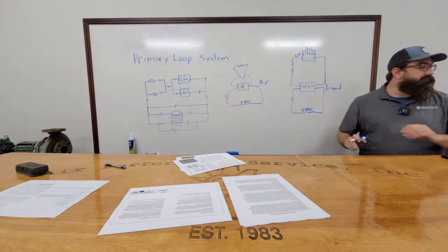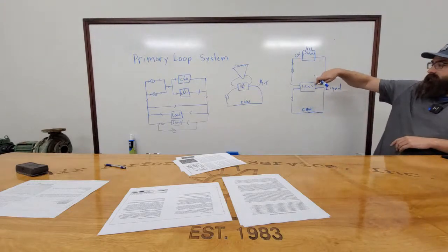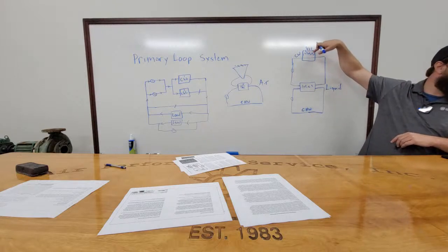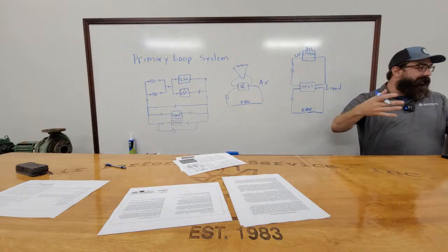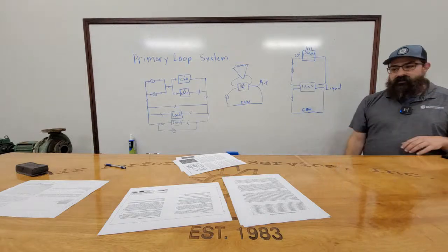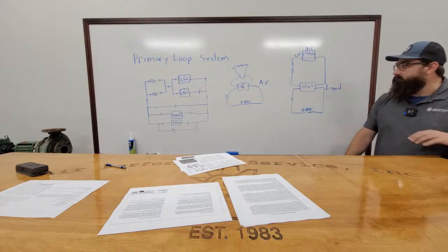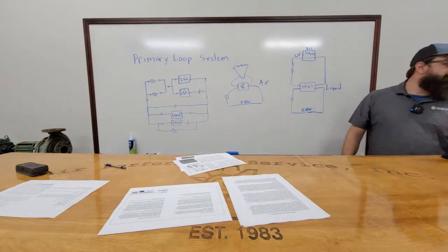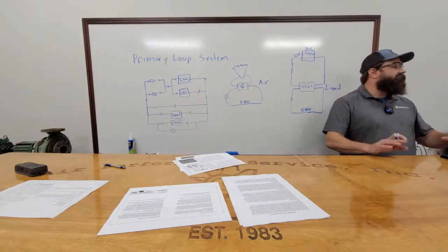Basic would be closed loop and open loop. Open loop, you are actually circulating the same water that goes through your chiller over this heat exchanger. Closed loop, you have a separate loop inside the cooling tower and a heat exchanger. It's the easiest way to explain it. There are some other variables that I don't know enough about to describe, like spray pump, no spray pump, that kind of stuff. But we're going to focus on the chill water side today.